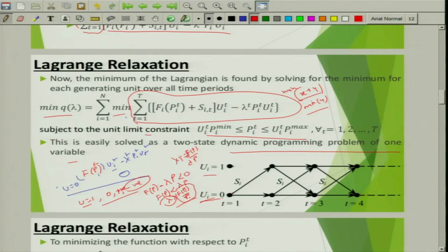So that means now this generator is giving you a hint that you better turn on me as a generator, turn on a generator such that the overall cost would be lesser than the previous lambda. You understand this point? So that means we are in a way considering the generator to be on so that we can reduce the operating lambda. That is what it means. Considering it to be on with a negative value is more economical than considering it to be in the off state, which gives a value of 0, right.